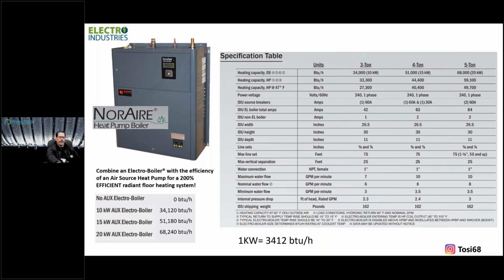So 10 kW is an additional 34,120 BTUs. Go up to 20, double it, 68,240. What does the envelope require, right? Heat loss. What is our heat loss or heat gain for summer? That's really what we need to start on every going-forward project.